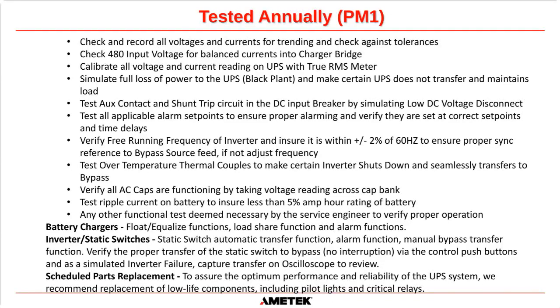Okay, so we check and record all the voltages and currents. We check the 480 input voltage for balanced currents into the charger bridge. We calibrate all voltage and current readings on the UPS with a true RMS meter. So whether they're analog meters or whether it's our digital display, we make sure that the values that we read with our meter are the same that are displayed on that system.